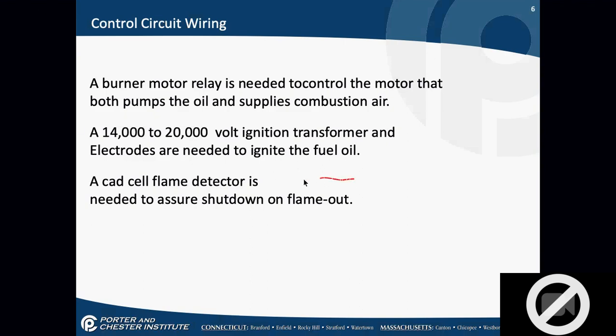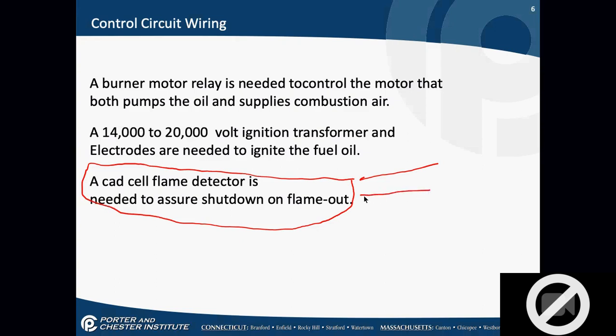Okay, real quick, I don't want to get into too much information on this without talking about the whole control system. This device right here senses light. It's a CAD cell flame detector. It senses light. It senses the flame. Okay? If the flame goes out, the CAD cell detector no longer senses light. It shuts down the burner motor. And therefore, it's no longer dumping fuel oil into the combustion chamber. It's a safety device. No flame, no light, no burner motor. Any questions on that? Nope.